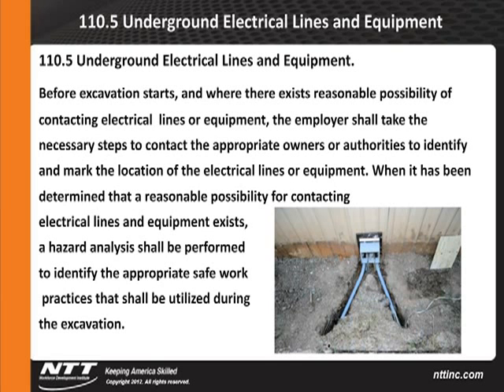New section 110.5. This has never been in here before. I've been asked many times in the past, what about underground? Well, in most of the states I've ever been in, if you're out there digging in the ground, you call Diggers Hotline, 3 days notice, and so forth. But what about on your own properties? Before excavation starts, and where there exists reasonable possibility of contacting electrical lines or equipment, the employer shall take the necessary steps to contact the appropriate owners or authorities to identify and mark the location of the electrical lines or equipment. When it has been determined that a reasonable possibility for contacting electrical lines and equipment exists, a hazard analysis shall be performed to identify the appropriate safe work practices that should be utilized during the excavation.